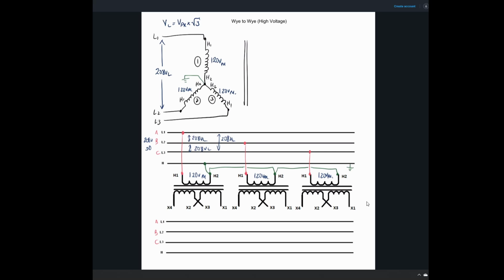Okay, so I believe that's everything for our primary circuit. Now we've got to do the secondary. We're doing the higher voltage, so we're going to do a series connection of our windings there. Double windings on the secondary. Line 1 would be fed off of this guy. Line 2 we'd pick up off that corner. And then line 3 is going to come off this guy. This one is bonded to ground as well. And we need our labels here, X1, X2, X3, and X4.